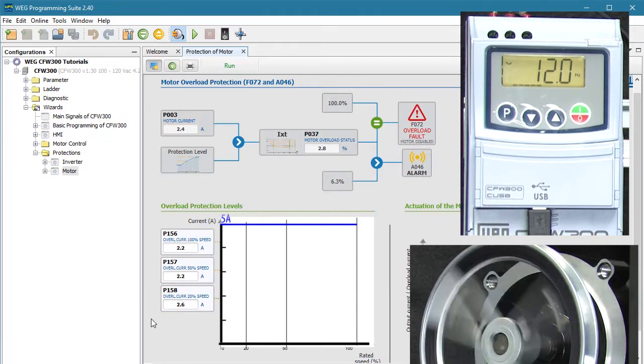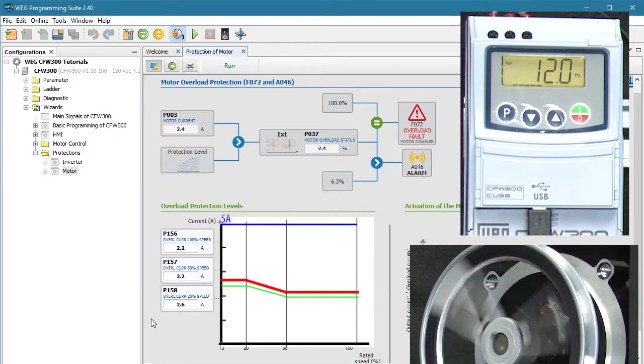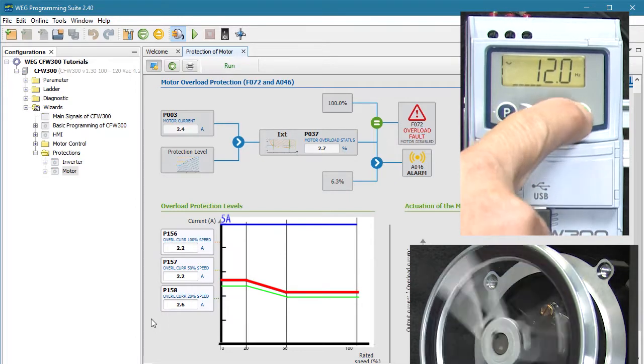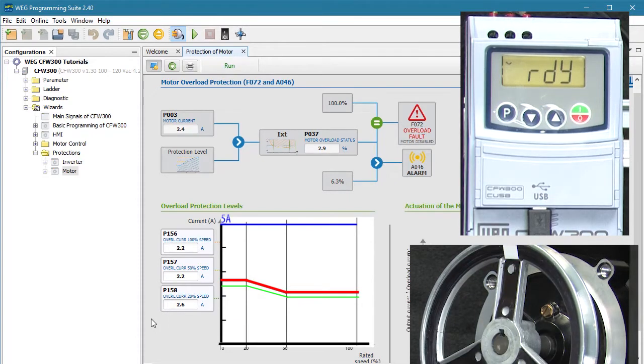So I'll put 2.4 amps plus 10%, or 2.6 amps, here. On our curve that would look like this, with the green line being our actual current and the red line being the overload limit we just set.